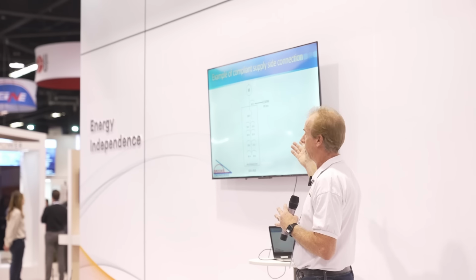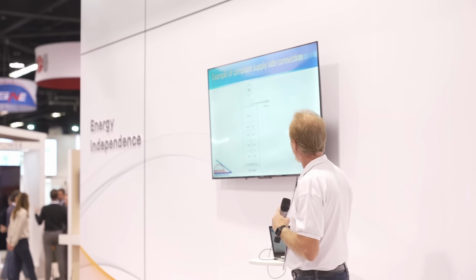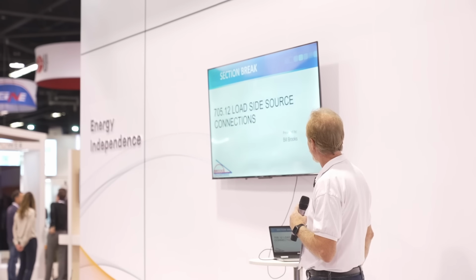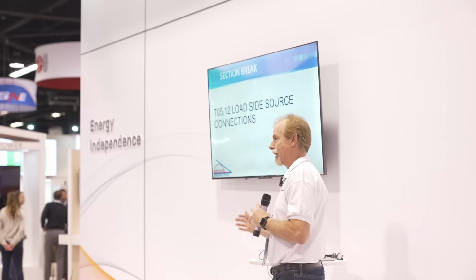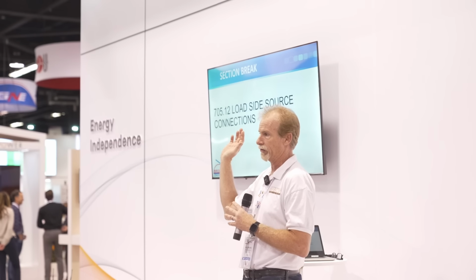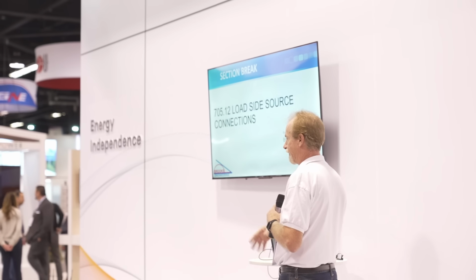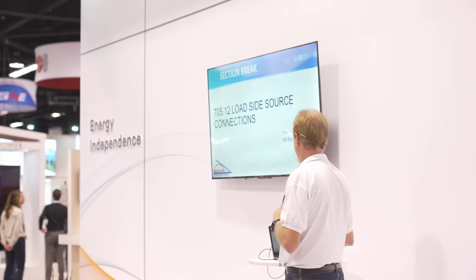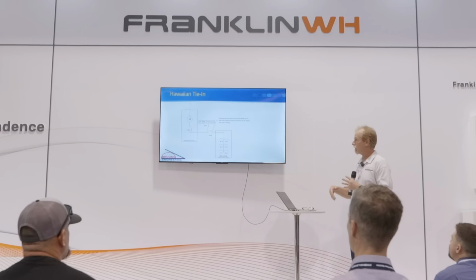Anyway, supply side connections, this is what we're going to talk about. And this is the extent of it. Hooking stuff into that is never going to happen again. We're just not going to do it that way anymore. So forget all the rules about supply side connections unless you're doing large commercial systems, and that's the only way you can do it. If it's got batteries, it's not going to be connected on the supply side. So everything's going to be load side.